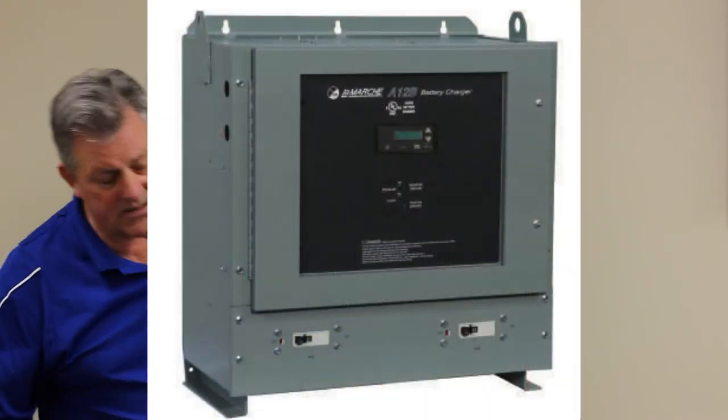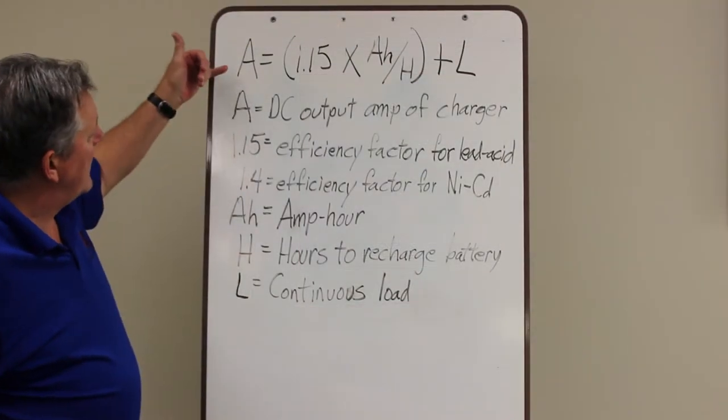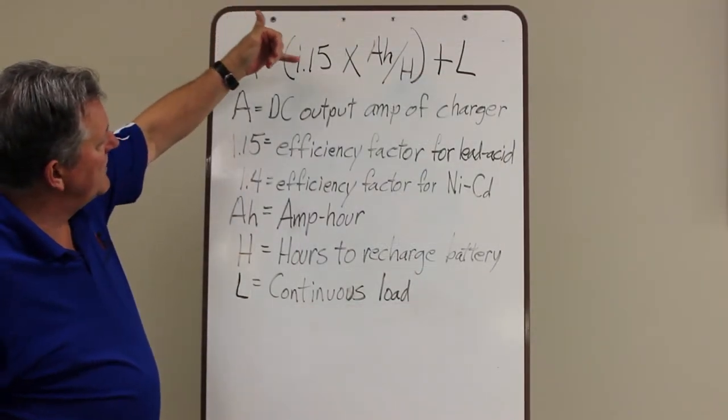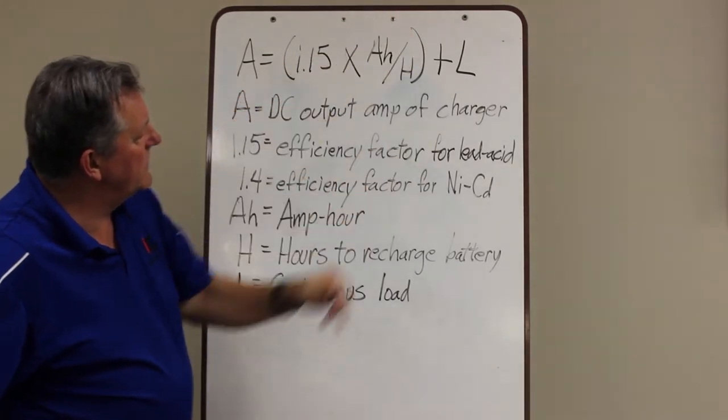So today we're going to look at sizing a battery charger. Pretty simple equation where A equals 1.15 times the amp hours divided by the hours plus the continuous load.